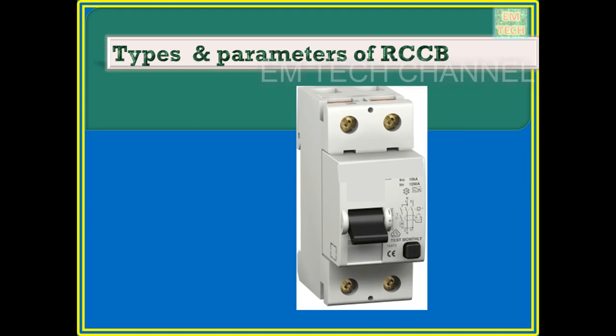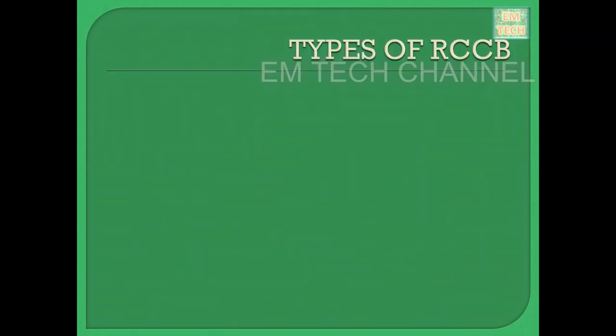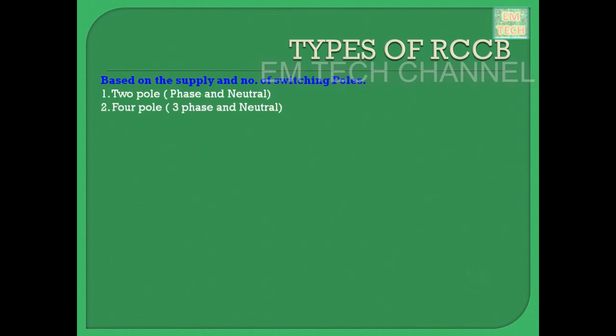Okay, let's move on. RCCB is divided based on four major categories, each having its own variants. First, based on the supply and number of poles, RCCBs are classified into 2 poles and 4 poles. A 2 pole consists of a phase terminal and a neutral terminal, intended for use in a single phase supply. Next is 4 poles, which consists of 3 phase terminals and 1 neutral terminal, and it is intended to use in a 3 phase supply.